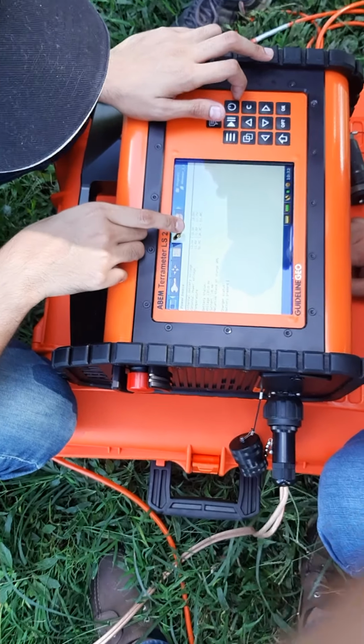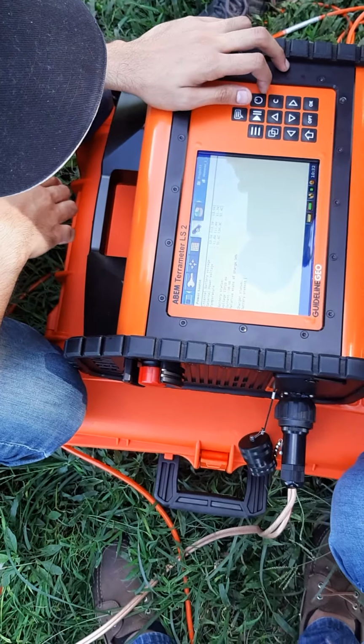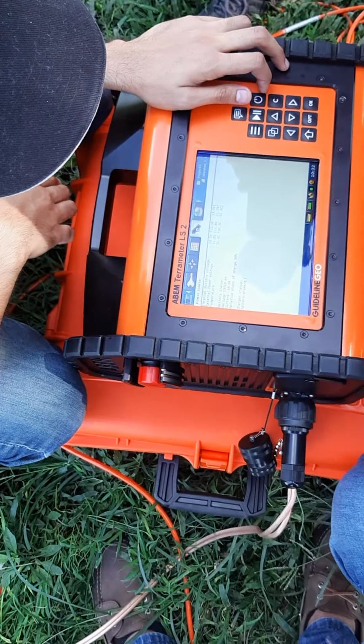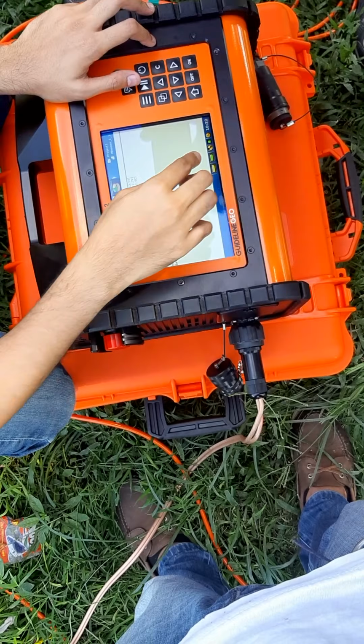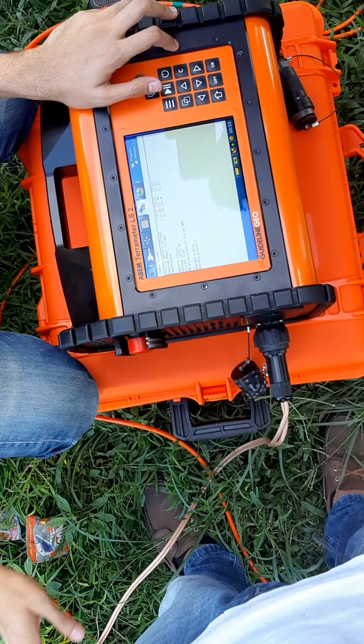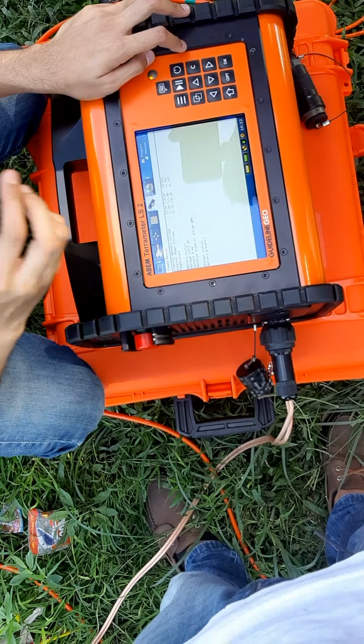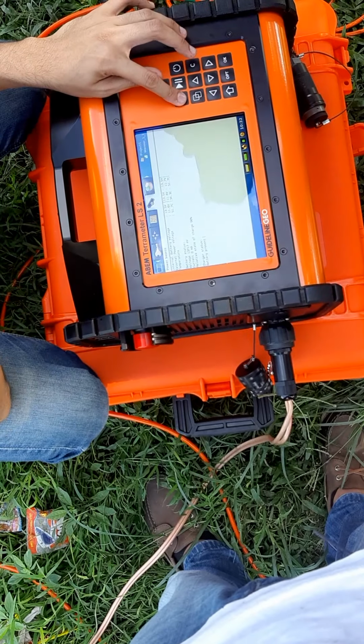The lower one is 34. So it's still diagnosing itself. If you charge, it shows your charging battery. If you have a full capacity battery inside here, it will charge the internal battery automatically. If you have a medium battery, it's not going to charge the internal one. Only the full charge will charge the internal. So that is the part of the instrument.